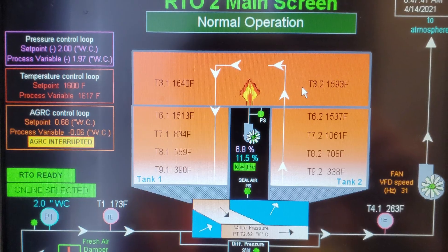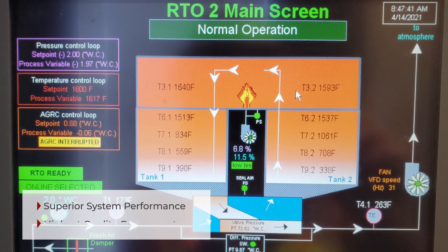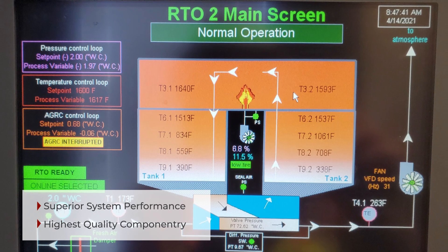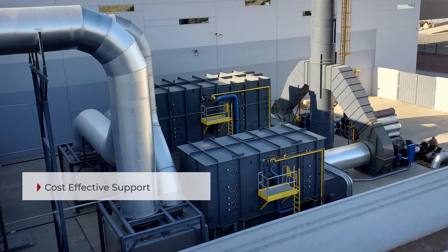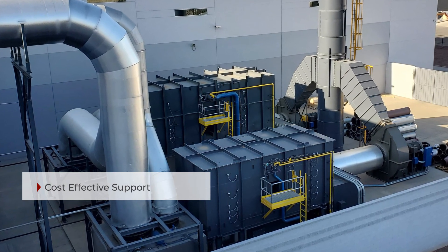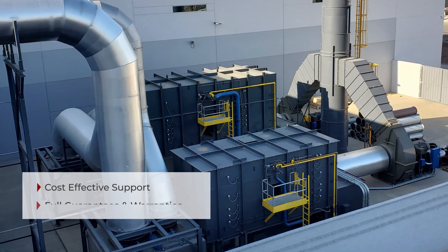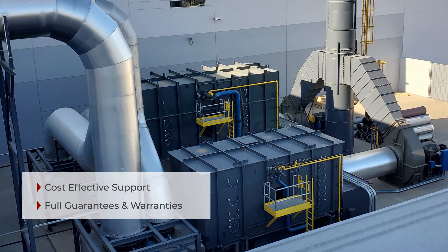An Allen-Bradley ControlLogix PLC and PanelView MMI was added in a fully redesigned and UL-rated control room. For process operating flexibility, innovative tandem operation was provided that included the addition of priority logic, additional isolation dampers for each RTO, and a common ductwork header design.